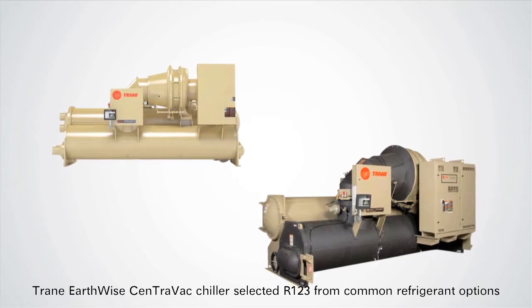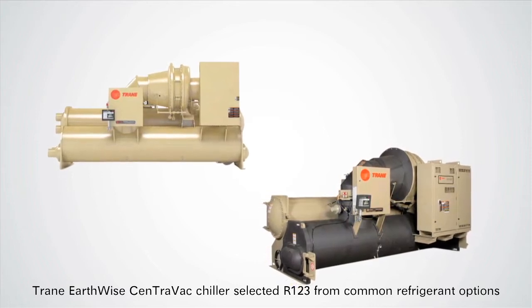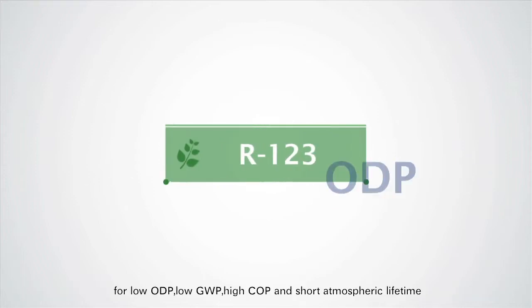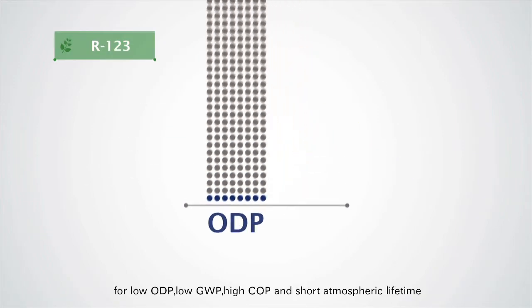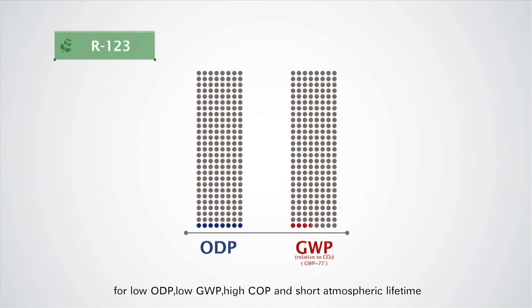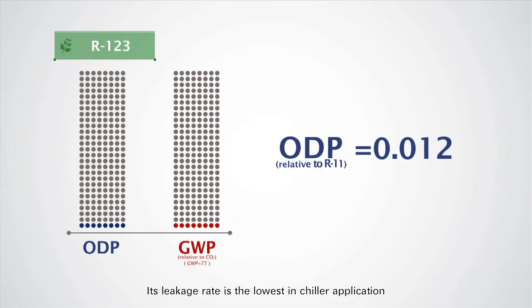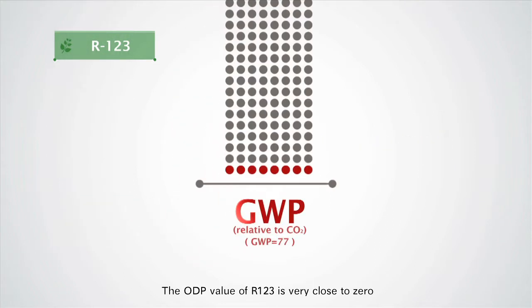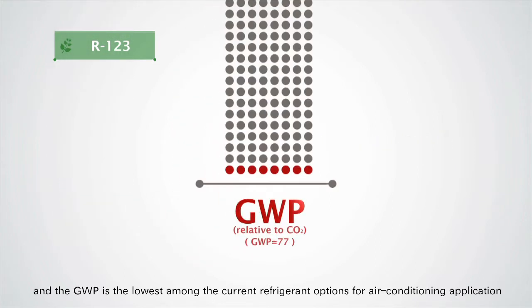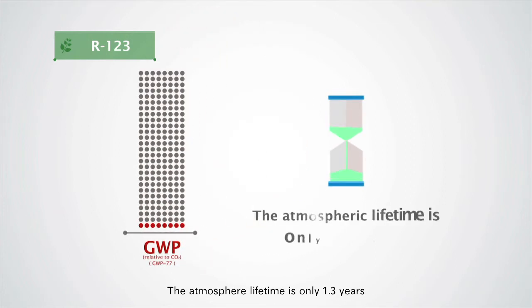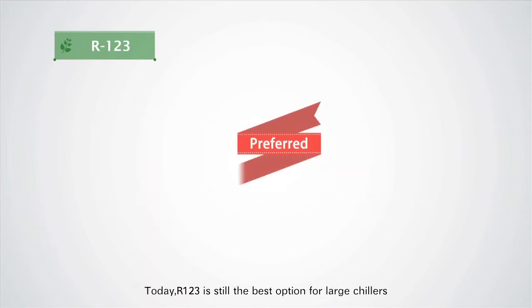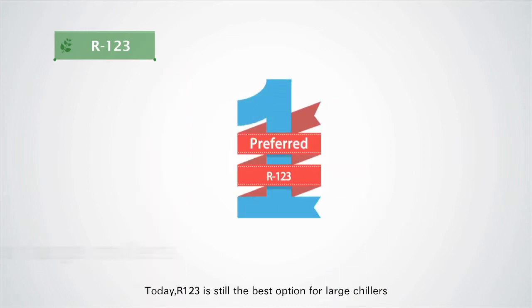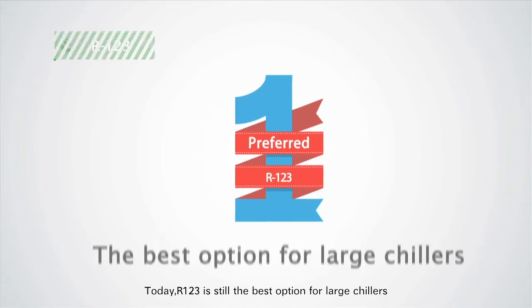Trane EarthWise CenTraVac Chiller selected R123 from common refrigerant options for its low ODP, low GWP, high COP, and short atmospheric lifetime. Its leakage rate is the lowest in chiller applications. The ODP value of R123 is very close to zero, and its GWP is the lowest among current refrigerant options for air conditioning applications. Its atmospheric lifetime is only 1.3 years. Today, R123 is still the best option for large chillers.